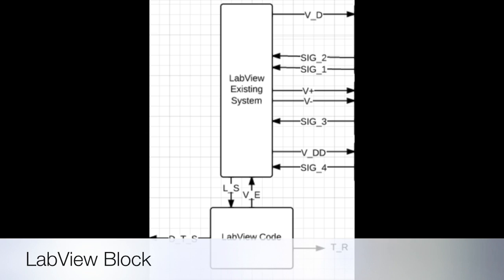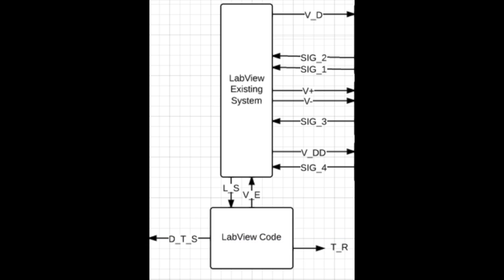Within the LabVIEW block is both the LabVIEW code and the LabVIEW existing system. The existing system sends out the control voltage to the sensors and reads in the adjusted voltage values from the sensors. These signals are converted to actual values in the LabVIEW code that can be easily displayed, transmitted to the control unit, and properly saved as a text file for analysis.